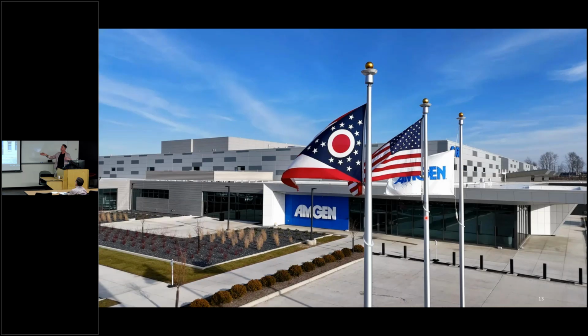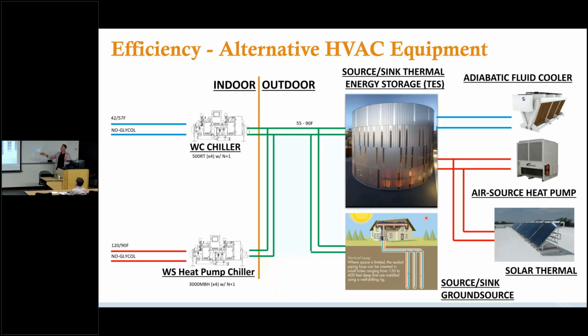A big part of that is thinking through which HVAC equipment you want to put in, in addition to the building envelope. With adiabatic fluid coolers, air source heat pumps, solar thermal, and especially solar with thermal storage, we can get rid of the cooling towers on the site. This does a couple things: it gets rid of a significant portion of a site's water consumption, which is a huge win, and it allows us to optimize those HVAC systems.